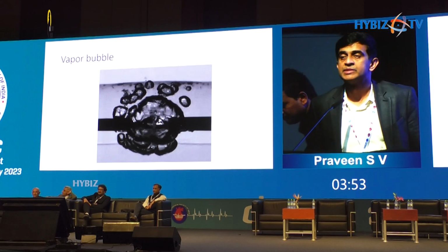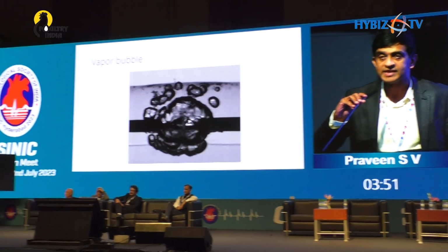The basic principle of intravascular lithotripsy is based on a vapor being created by electrical energy and the further propagation of mechanical waves. So what basically happens in an IVL is, it's not a balloon. Basically, there are two emitters which give electrical energy, and you have a fluid-filled balloon where this is converted to acoustic waves, and that is transmitted through this interface into the vessel wall, cracking the calcium. So this chart shows a basic principle, and we know that waves have a positive and negative deflection.